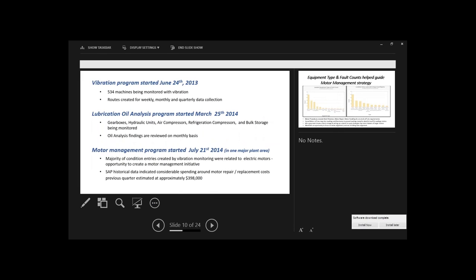We wrote some procedures on minimum requirements for purchasing motors or rebuilding motors. By setting up that standard, we let the maintenance people know that we were going to start requiring certain steps to be taken before we changed a motor or before a motor was rebuilt. With the procedures in place, we also went out and we surveyed three of the local motor shops and determined the condition of their shops. And we let them know that we now had a minimum standard that they would adhere to if they got the bid to repair the motors. And along with that and the inventory clean up and just basically putting an eye on each and every motor out in the plant, we actually turned it around in about 18 months.